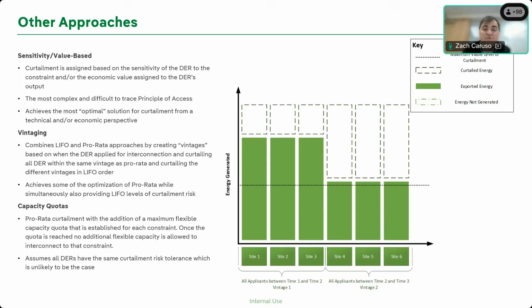And to combat that, what we're proposing right now is a capacity quota approach, where we would establish a maximum amount of capacity we would accept. And that provides both a technical cap, right? Like I said, we don't want 50 megawatts on a 20 MVA bank. And it also provides some degree of curtailment certainty that we think is necessary to continue to implement these sites.